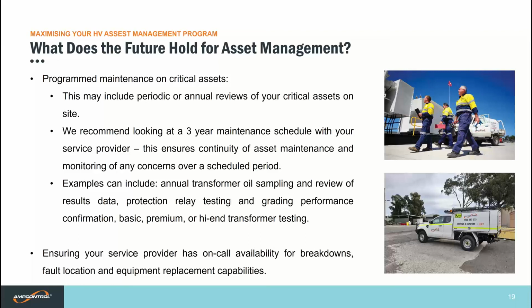For program maintenance on critical assets, this may include periodic or annual reviews of your critical assets on site. We would recommend looking at a 3-year maintenance schedule with your service provider. This ensures continuity of asset management and monitoring of any concerns over a scheduled period. Examples can include annual transformer oil sampling and review of results and the data that's required from those sampling. Protection relay testing is another one, and grading performance confirmation, basic, premium or high-end transformer testing. Ensuring a service provider has on-call availability for breakdowns, fault location and equipment replacement capabilities.